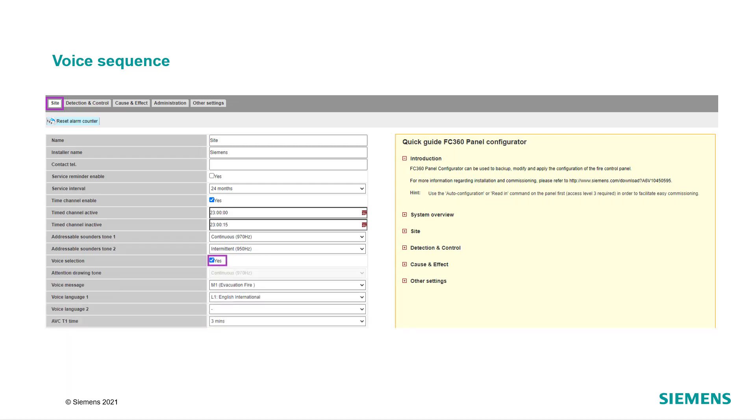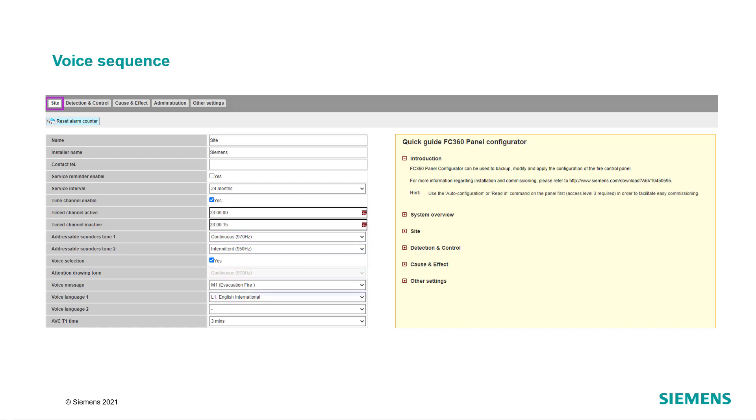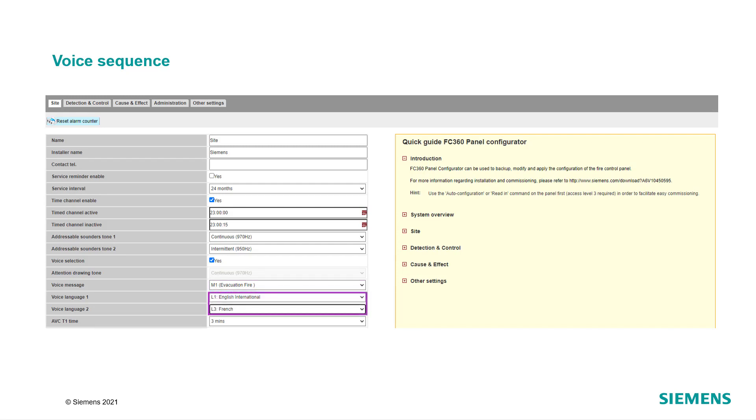Activate the voice selection option in the menu. The attention drawing tone will be selected automatically by the tool. It is the same as the addressable sounder tone 1. Select which message should be played when the voice sounder gets activated: evacuation fire or evacuation emergency. As the last step, select the language to be played. If you would like to use only one language, leave the field for the second language empty.